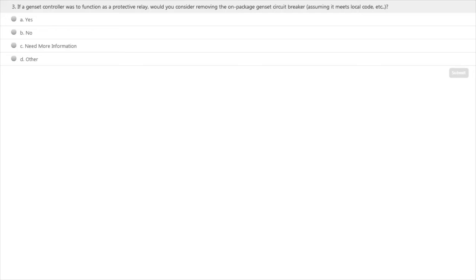It would be recommended that you work with your local dealer on those discussions because you are going to want to have a physical disconnect somewhere close to the generator for maintenance and to be able to remove it from the system. So you want to make sure that you coordinate that, and some codes will have a specific distance that they require that physical disconnect. But from a UL standpoint or a certifying body standpoint, it's often that we can get approvals to be able to ship packages without a package mounted breaker.